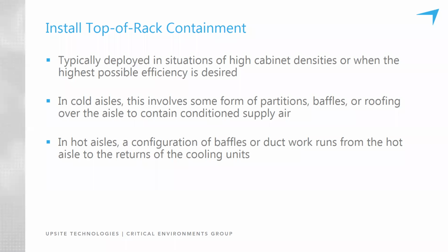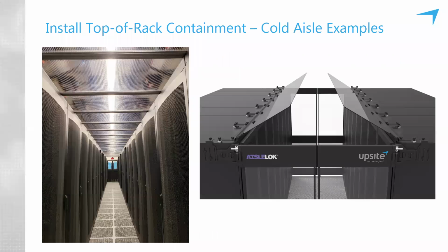They're always going to provide some improvement and enable the further reduction of fan speeds and potentially raising cooling unit set points to further optimize the room. In cold aisles, they look like baffles or a full roof. And we're going to show you some examples of those here.